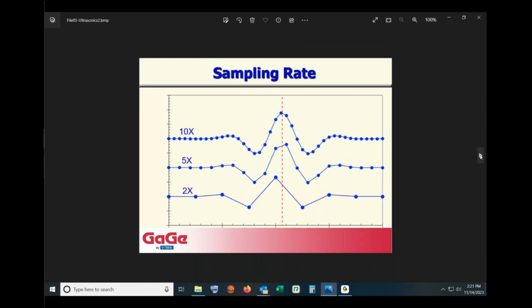So the two banner specifications of a digitizer are its sampling rate and its resolution. The sampling rate is important in ultrasonics to the extent that it allows us to determine the position in time of ultrasonic echoes. So here I've shown a typical ultrasonic echo. Yes, it's mathematically generated, but it could be a real ultrasonic echo, sampled at a relatively low speed on the bottom image. So what we've done here is satisfy what we call the Nyquist criteria, which many of you may have heard of, which is a mathematical requirement that you must sample at least twice a signal's maximum frequency in order to follow that signal and not have its frequencies aliased or distorted to lower frequencies.